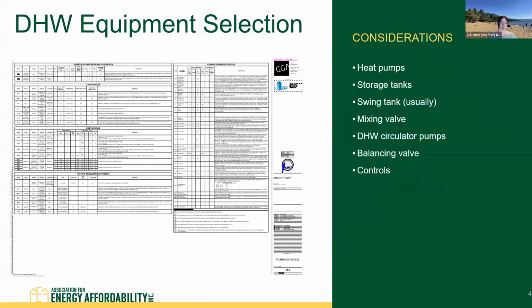All right, the first thing we're going to cover is equipment selection. Throughout this, I'm going to be illustrating some of these concepts with our case study from Union Tower. It's got a central heat pump water heating plant. Also, I'll be focusing on central systems, but keep in mind that unitary heat pump water heater designs, meaning one water heater per apartment or unit, are also common and appropriate for many buildings, particularly low-rise garden-style buildings.